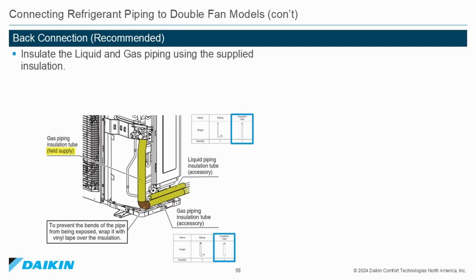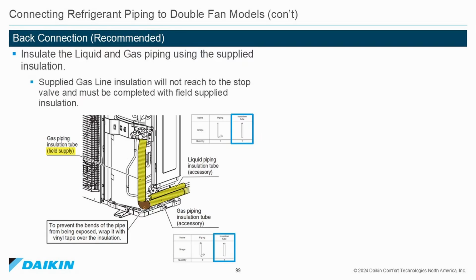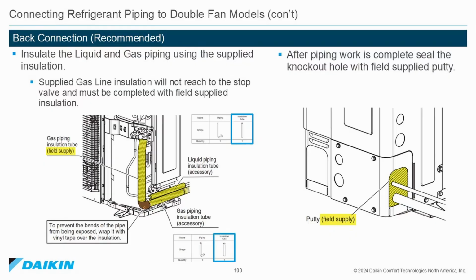Back connection, which is the recommended connection. Insulate the liquid and gas pipe using the supplied insulation. To prevent the bends of the pipe from being exposed, wrap them with vinyl tape over the insulation. The supplied gas line insulation will not reach the stop valve and must be completed with field supplied insulation. After the piping work is complete, seal the knockout hole with field supplied putty.